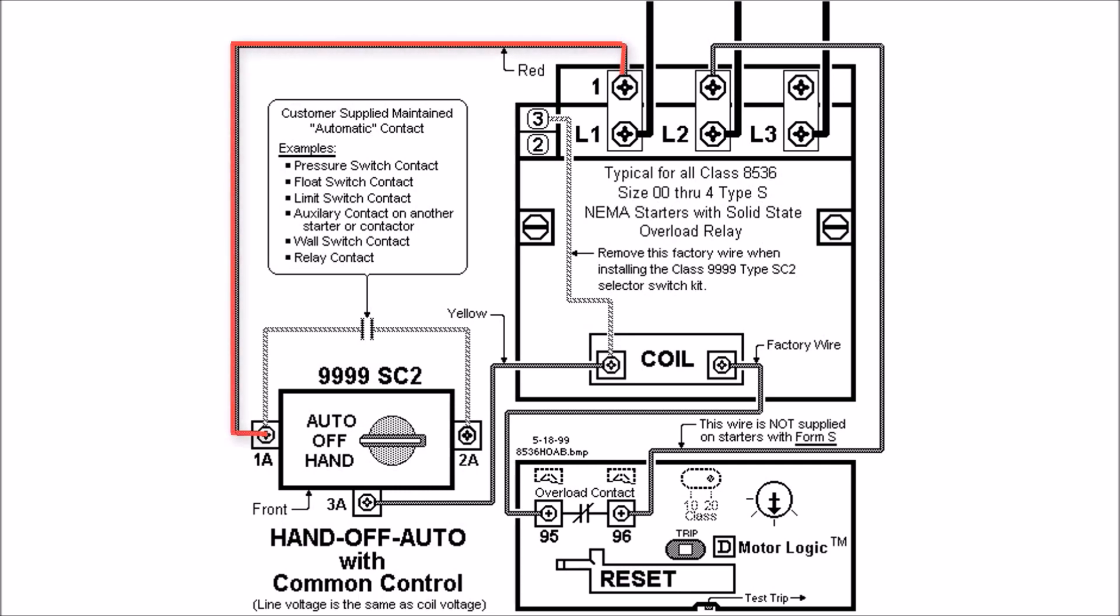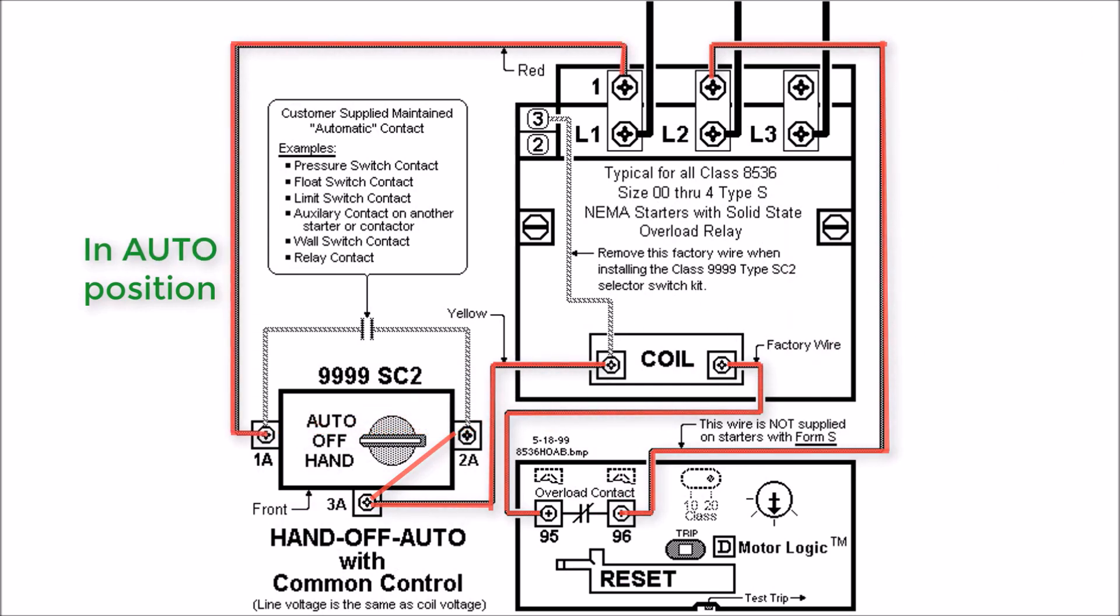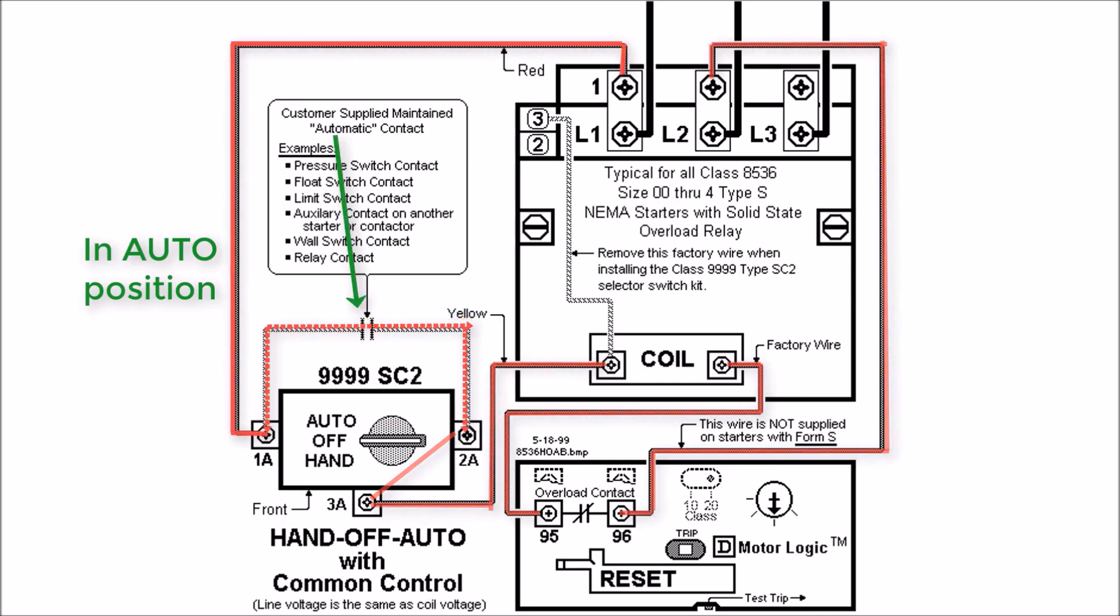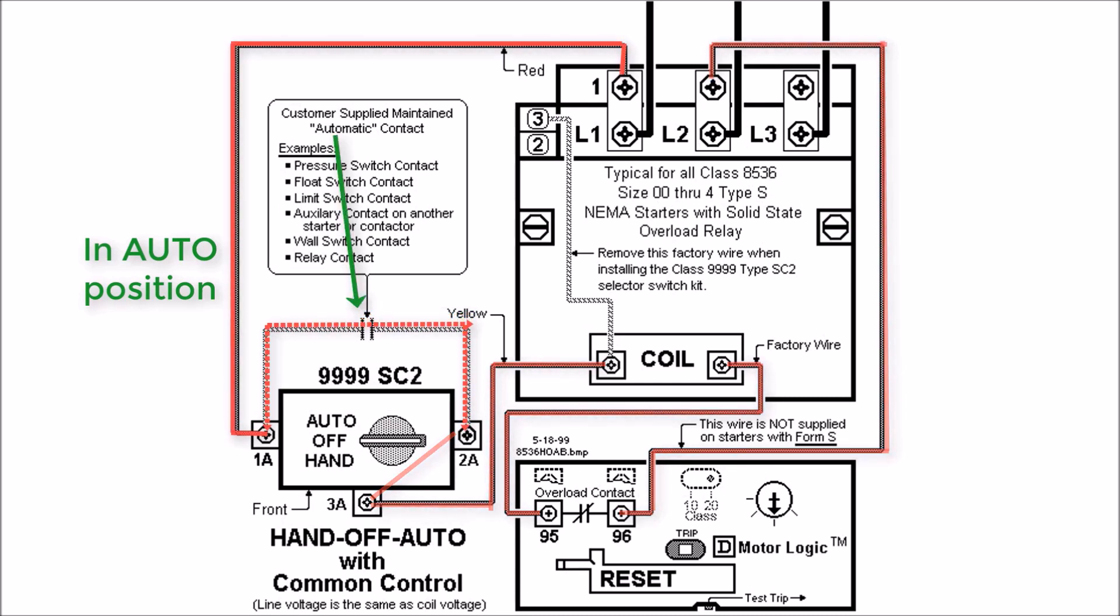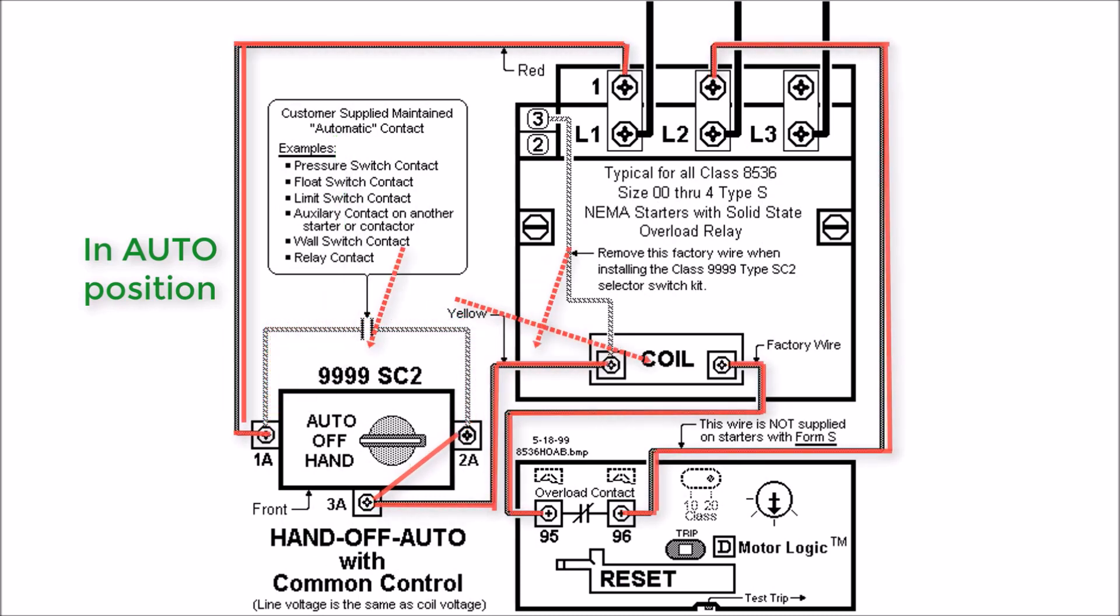It's basically the same principles as a separate source, where 1A to 2A will close in hand, sending voltage to your coil. In auto, you'll have your switch, your normally open supplied contact or your automatic contact will be the jumper point from 1A to your contact, back to 2A. And that'll complete your circuit to the coil and engage your coil.